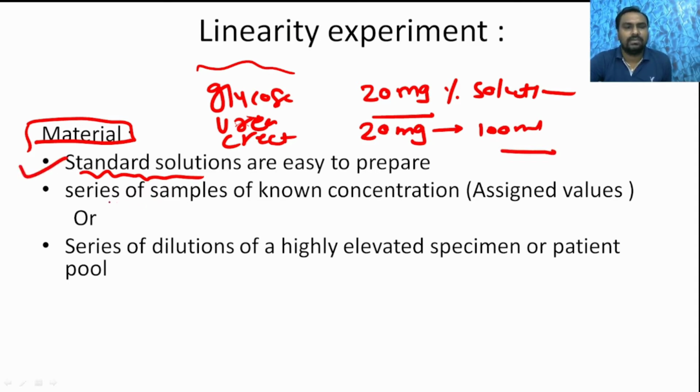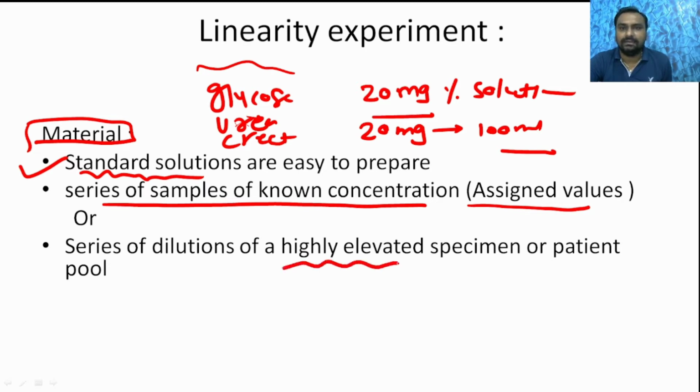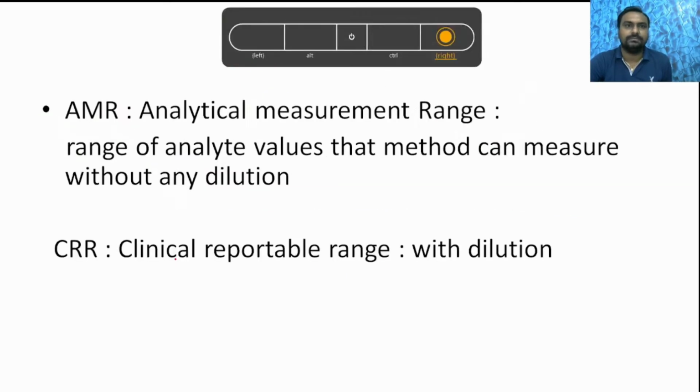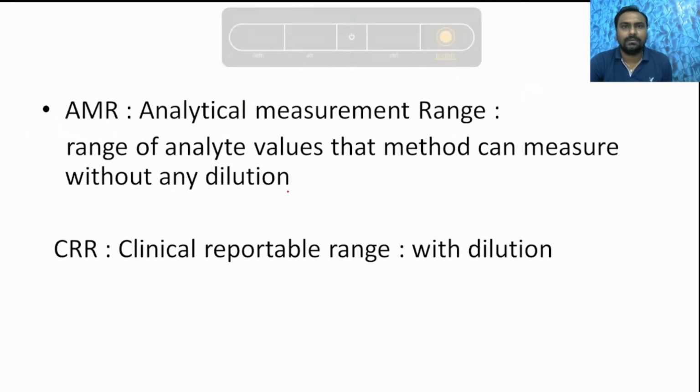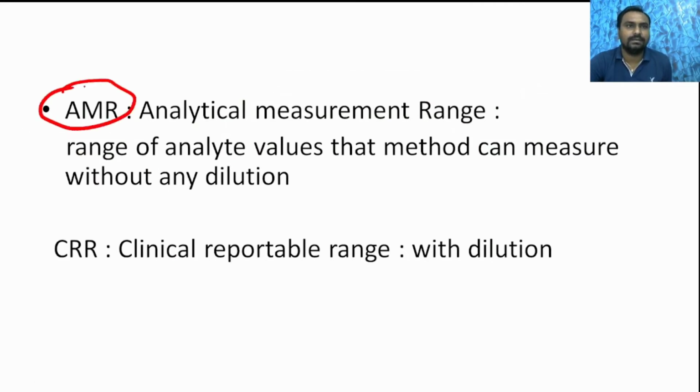Or we can use a series of samples of known concentration, with assigned values by the manufacturer. Or we can take a highly elevated specimen, or a patient pool of highly elevated specimens, and make a series of dilutions.